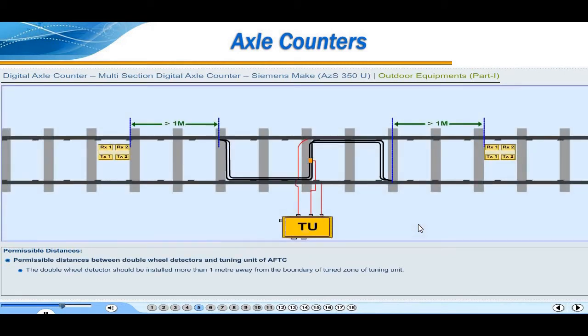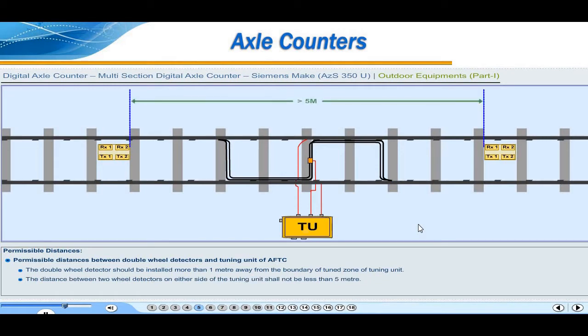Permissible distances between double wheel detectors and tuning unit of AFTC. The double wheel detector should be installed more than 1 meter away from the boundary of tune zone of tuning unit. The distance between two wheel detectors on either side of the tuning unit shall not be less than 5 meters.